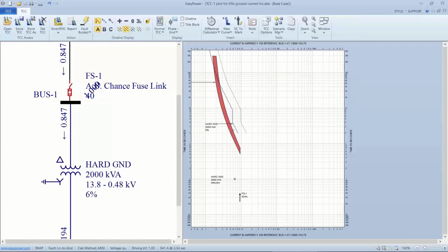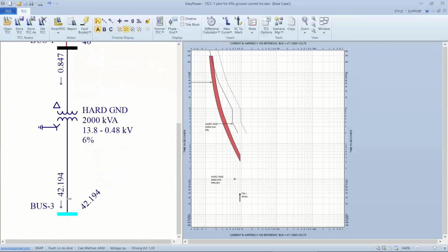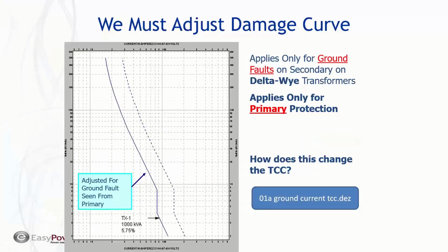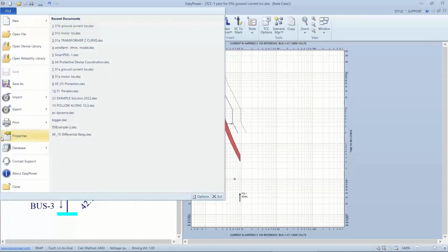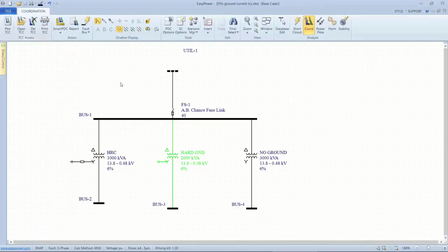I did a poor job of explaining that, but the point is, normally on a three-phase fault, I could set my current up to protect against a three-phase fault and never hit the frequent fault curve here. But on a single line to ground, which is what we're looking at, and a fault here, that 847 amp protection needs to be reduced so that it doesn't exceed this derated curve. Okay, I could have done better on that, but let's see what else I wanted to do. I do want to compare all three. So I want to look at the three plots for the high resistance ground, right?